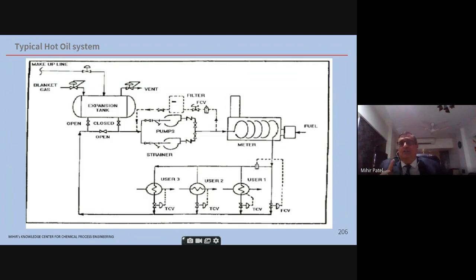Why is this Dowtherm used? Because you cannot use steam at such high temperatures. The pressures of steam are so high that your melt line design would be so thick, you would not be able to engineer it properly. Now that's a vapor system.